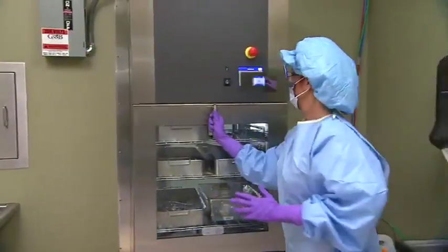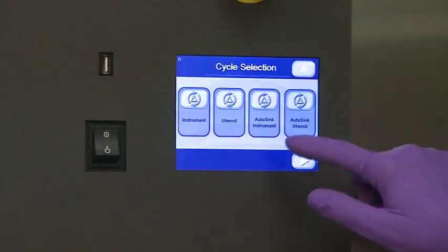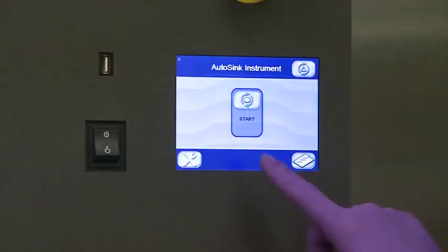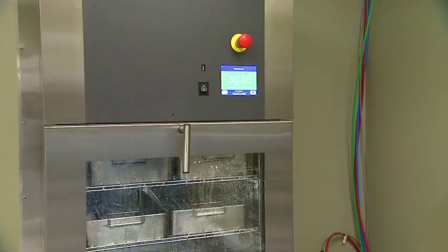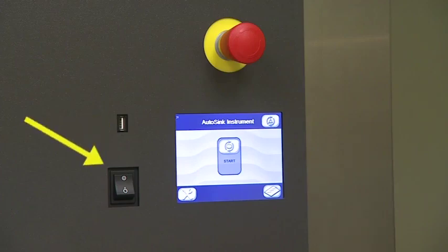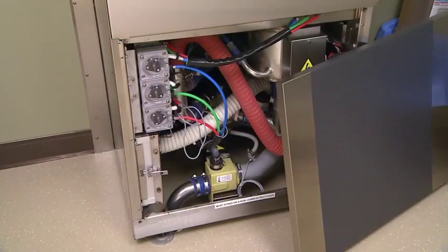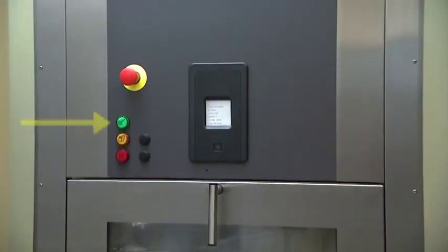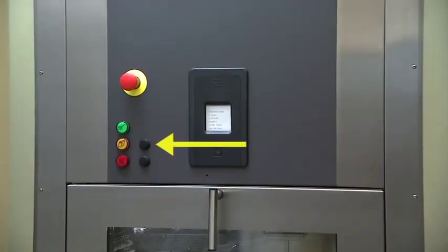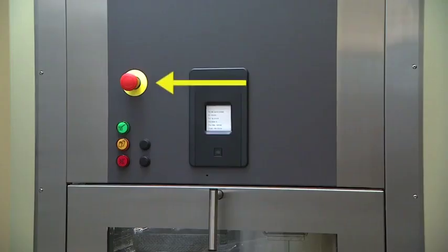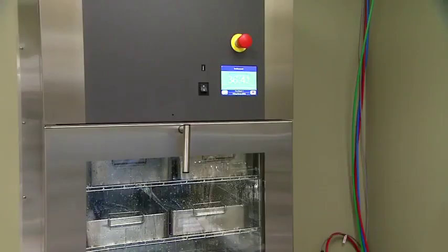On the load side, you'll notice an icon-based control screen for performing various cycle operations. We'll cover the functional aspects of the control screen in a moment. The load side also contains a USB port, an on-off switch control, an emergency stop button, and access panels for performing maintenance. On the unload side are indicator lights, two acknowledgement push buttons, an emergency stop, and, if selected, an optional printer. If you're using the single-door model, your unit comes equipped with all load side features.